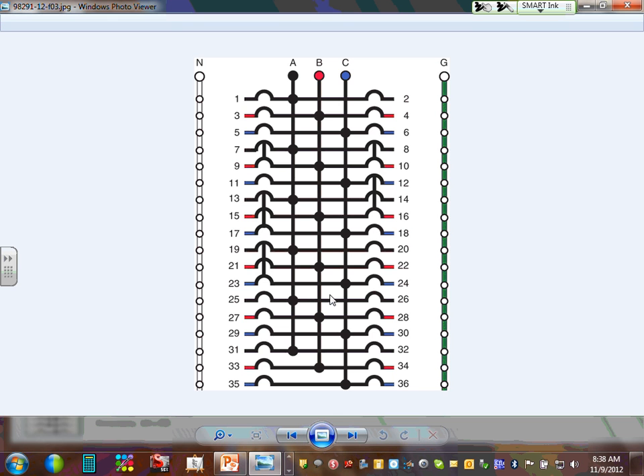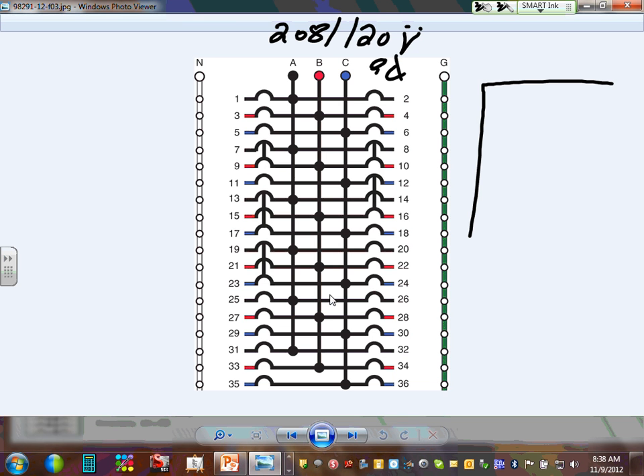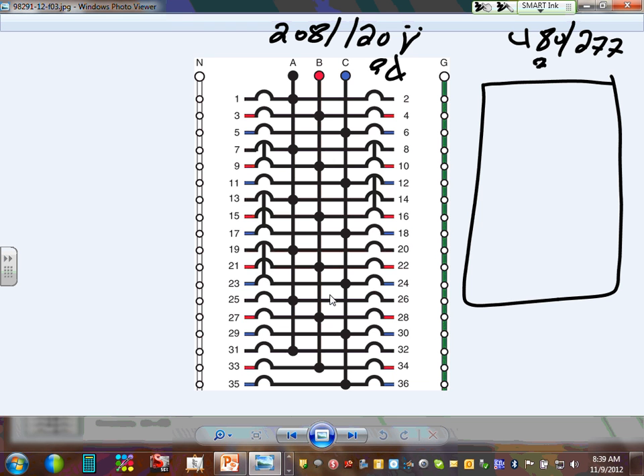if you have a building with 2 different voltages, by code, you have to identify the branch circuits and the feeders. So here's a panel. This panel, I have to identify it as 208/120 volt 3-phase panel. Right next to it here, I have a 480/277 3-phase panel. This panel is 400 amp. This panel, let's just say it was 200 amp. The building has 2 voltages.